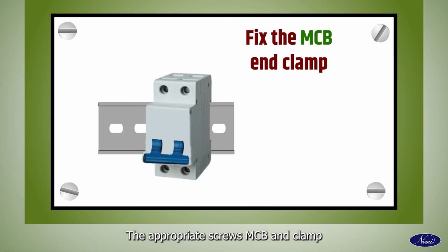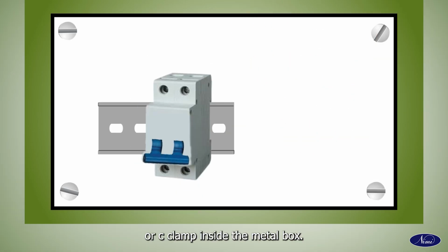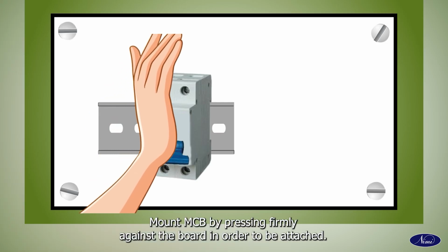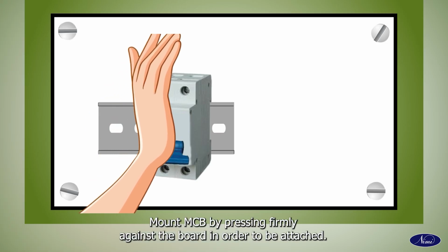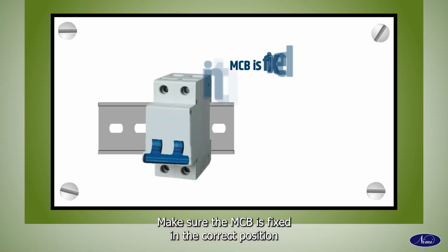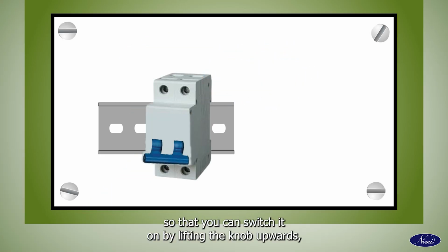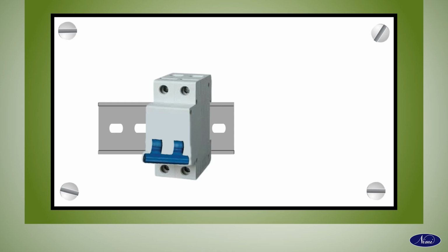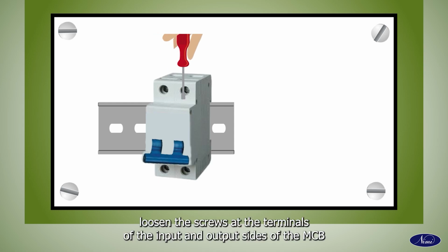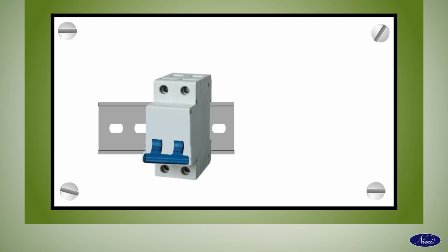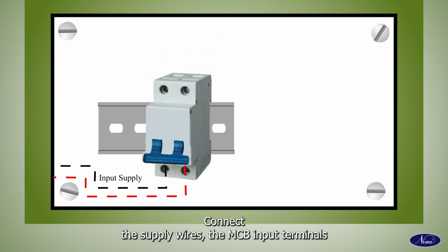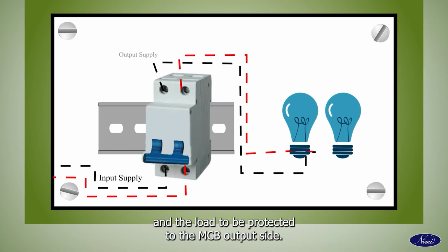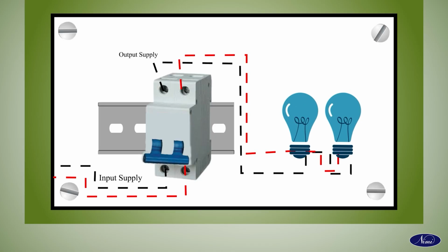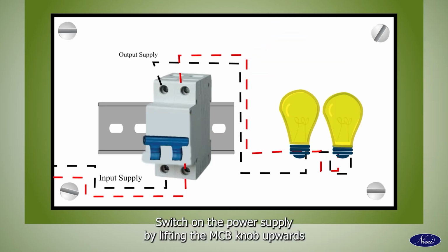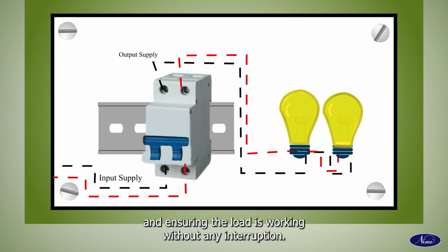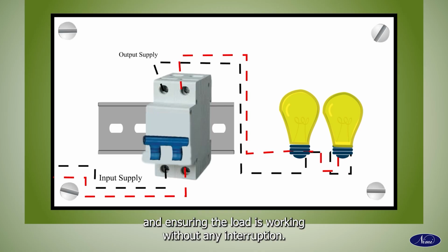Fix the MCB end clamp or C-clamp inside the metal box. Mount the MCB by pressing firmly against the bar in order to be attached. Make sure the MCB is fixed in the correct position so that you can switch it on by lifting the knob upwards. Loosen the screws at the terminals of the input and output sides of the MCB. Connect the supply wires to the MCB's input terminals and the load to be protected to the MCB's output side. Switch on the power supply by lifting the MCB knob upwards and ensuring the load is working without any interruption.